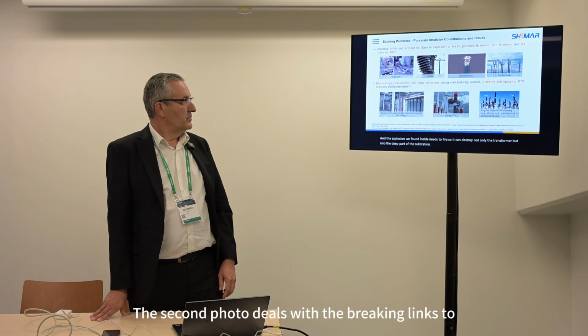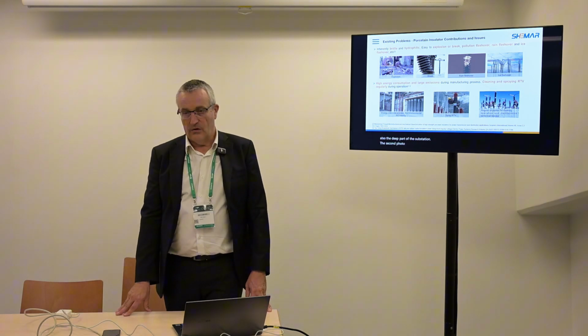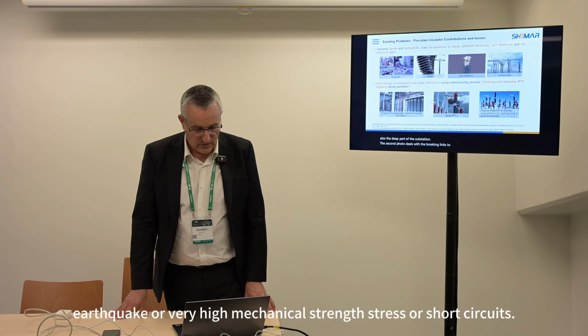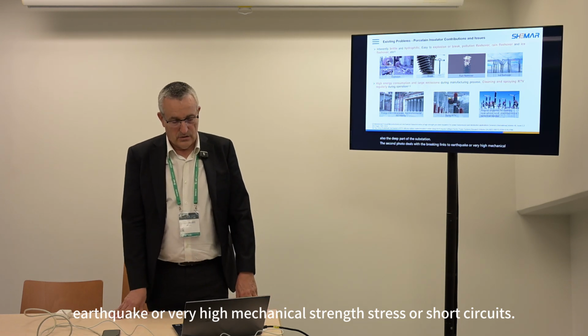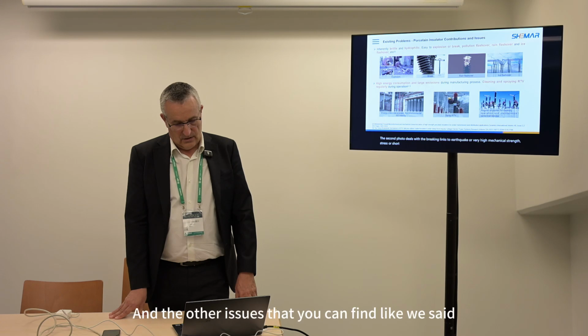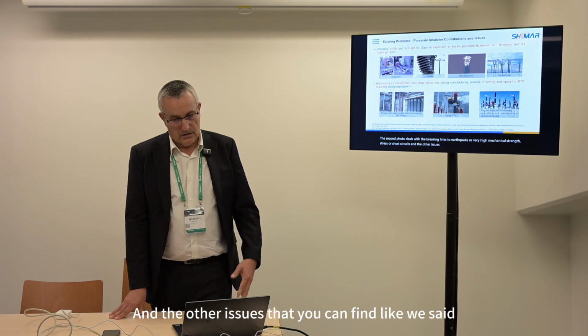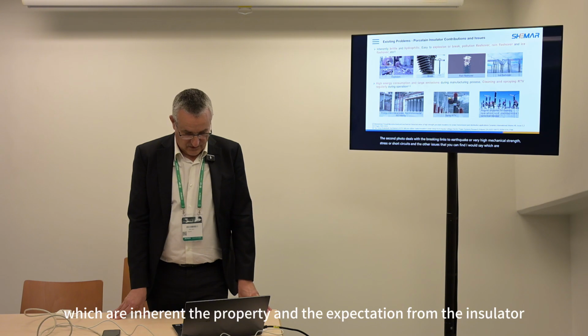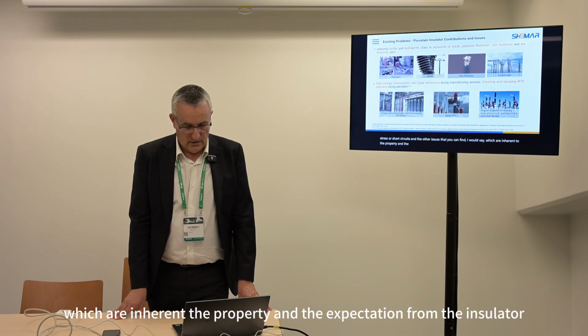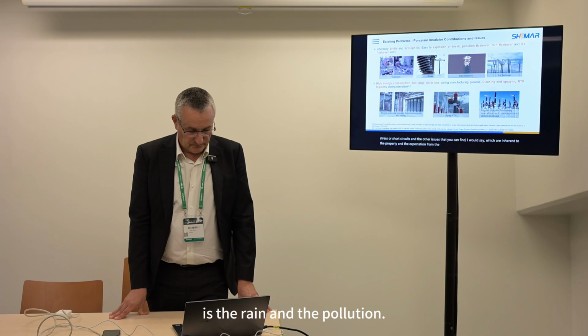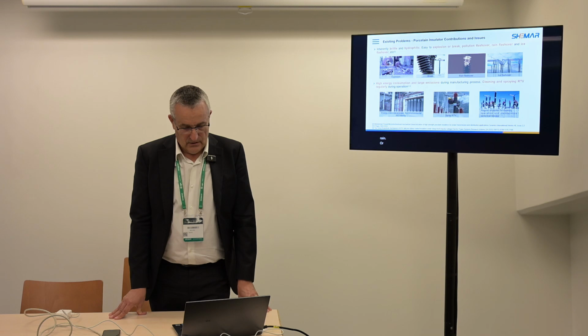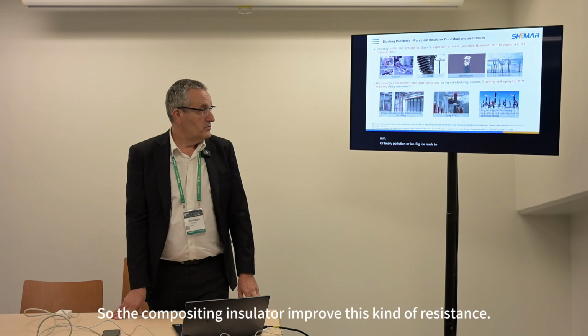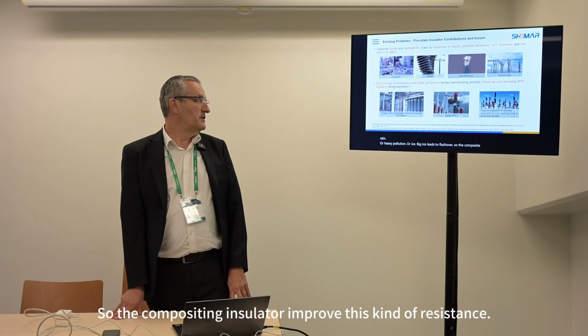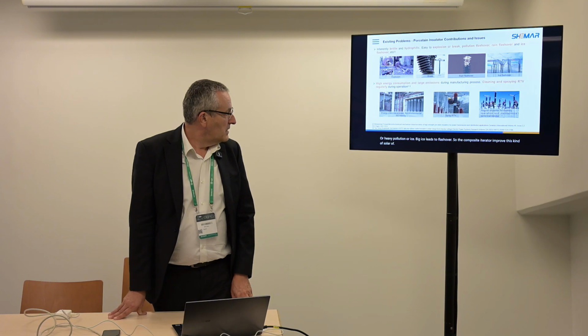The second photo deals with breaking linked to earthquake, very high mechanical stress or short circuits. And the other issues that you can find, which are inherent to the property and the expectation from the insulator, are rain and pollution. So heavy rain, heavy pollution or ice, big ice, leads to flashover. The composite insulator improves this kind of resistance.